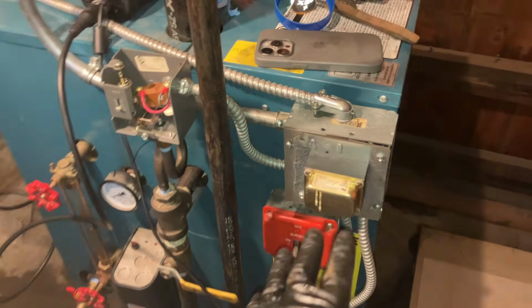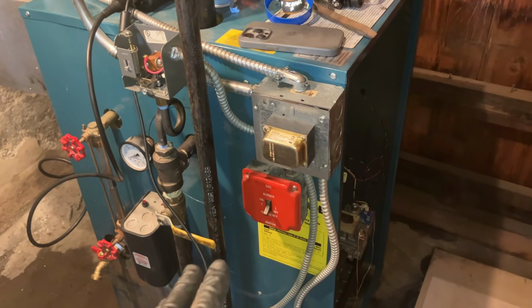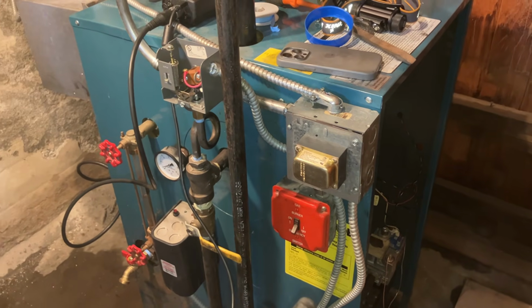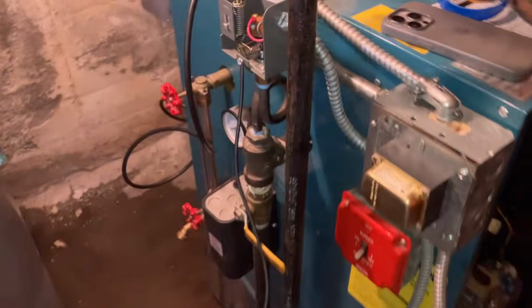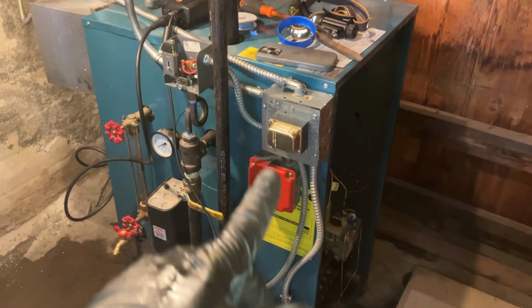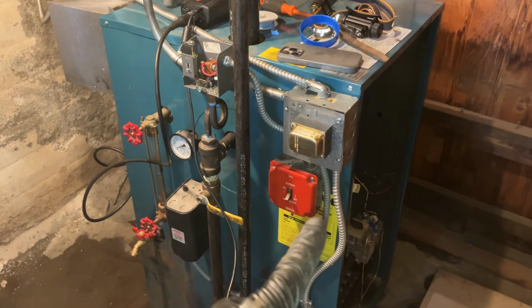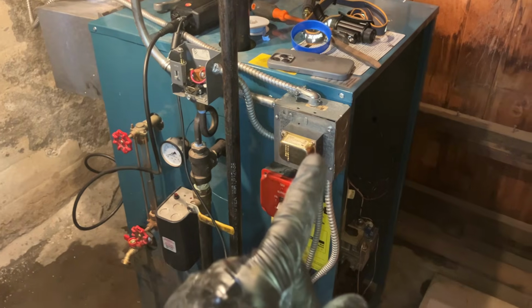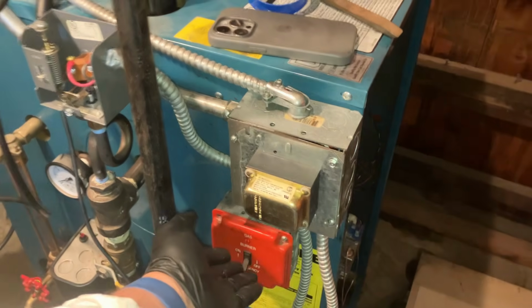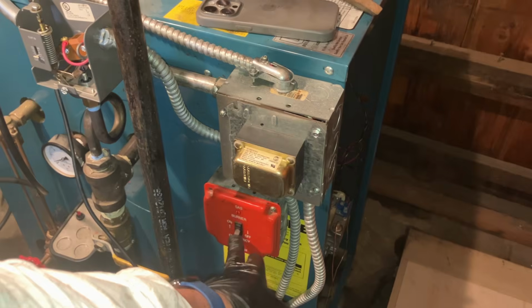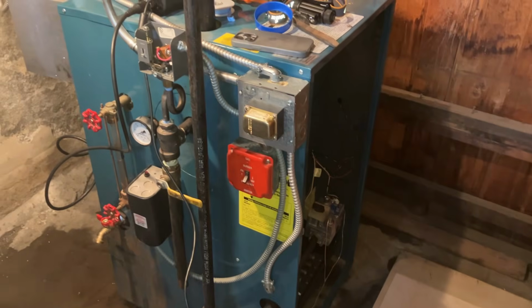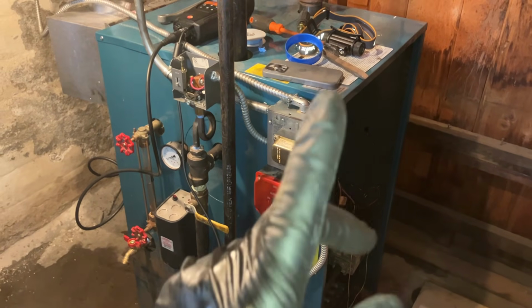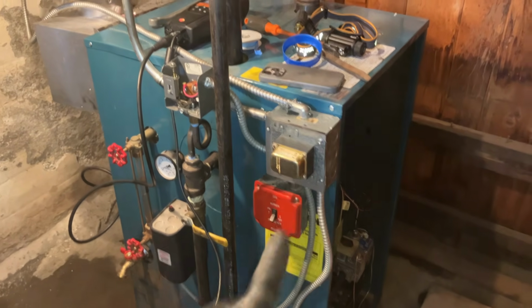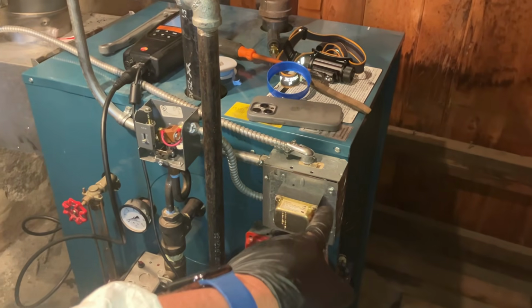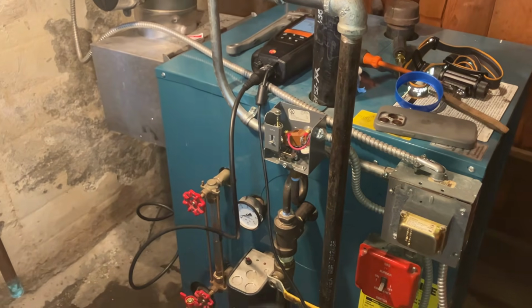Now, a couple things are going to happen. If the thermostat is not calling, the thermostat relay, which is sitting right here, is not going to do anything. If the thermostat is calling and our safety circuit is good, we are going to hear a click. Hear that click? That was the thermostat relay because we have an active call for heating. Now, once that thermostat relay is calling, we're going to have power to our safety circuit.